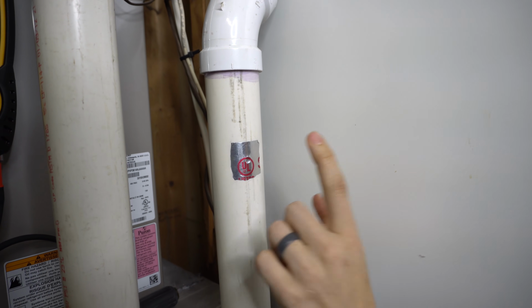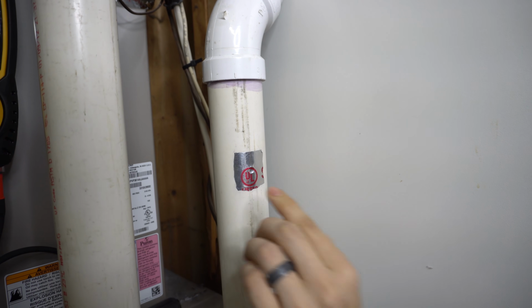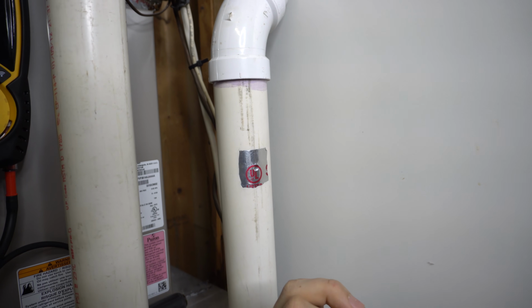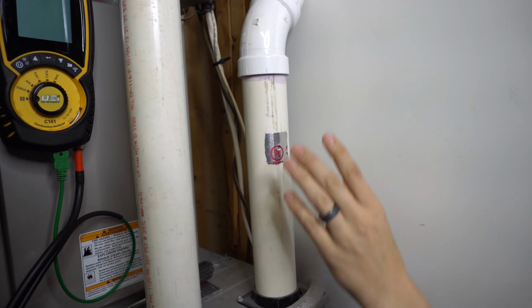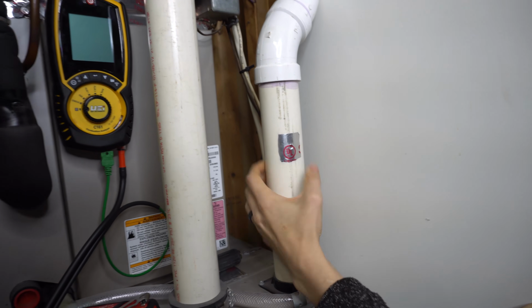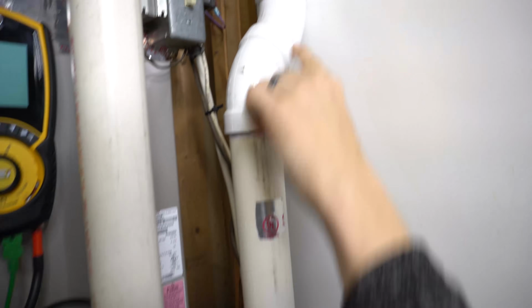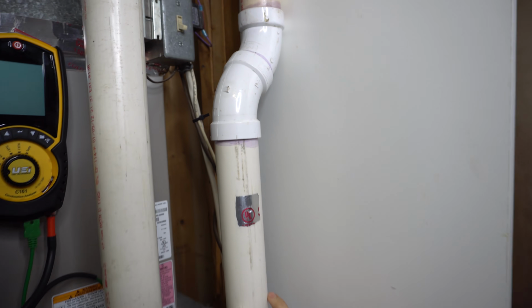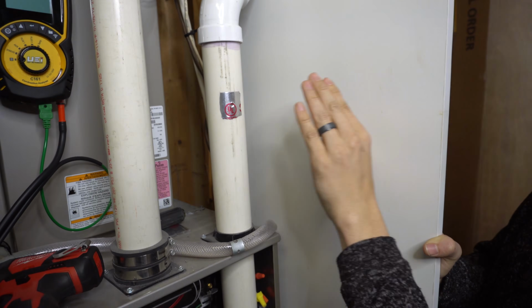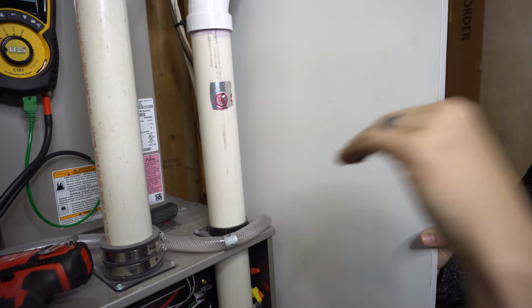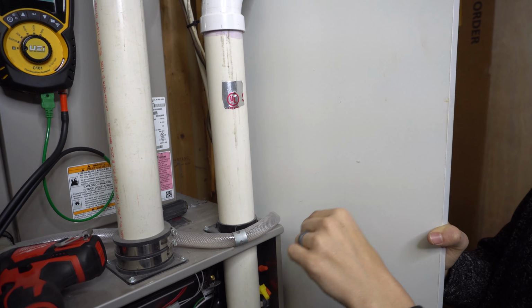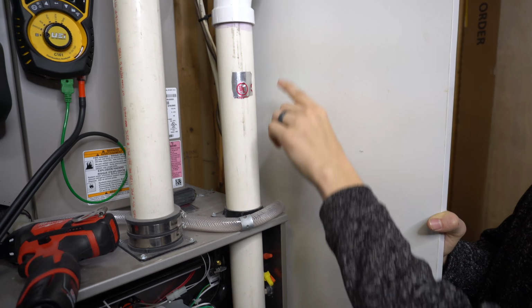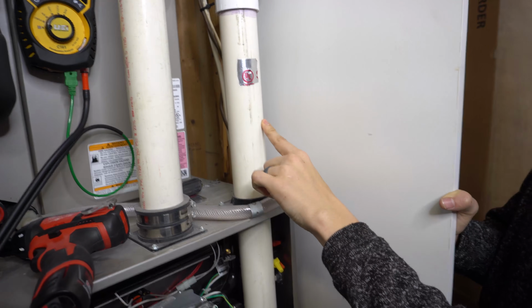But basically, where you want to drill the hole is the opposite side of where the water will be flowing. What I mean by that is, high efficiency furnaces condense, they create water. So there's going to be water that is constantly, slowly running back down this pipe. On high efficiency furnaces, the exhaust pipe is on a gradual downward slope towards the furnace. So there's always going to be some water trickling down the inside of the exhaust pipe.